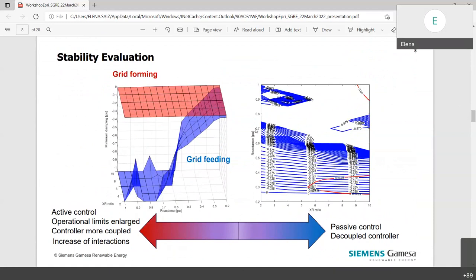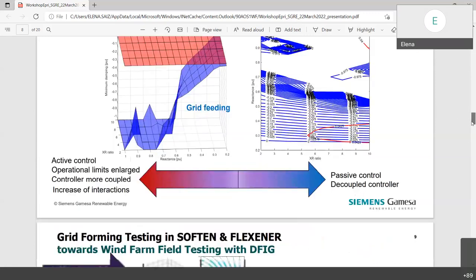As a brief summary, if we compare grid feeding versus grid forming, it's clear that with grid forming we are going to have more active control, and by doing that we are going to enlarge our operational limits. But it's also true that the control is a little bit more coupled, and we should be careful because it could increase the interaction with other elements. With grid feeding, the controller was really decoupled and we had a passive control, so those interactions with the rest of the system did not exist.